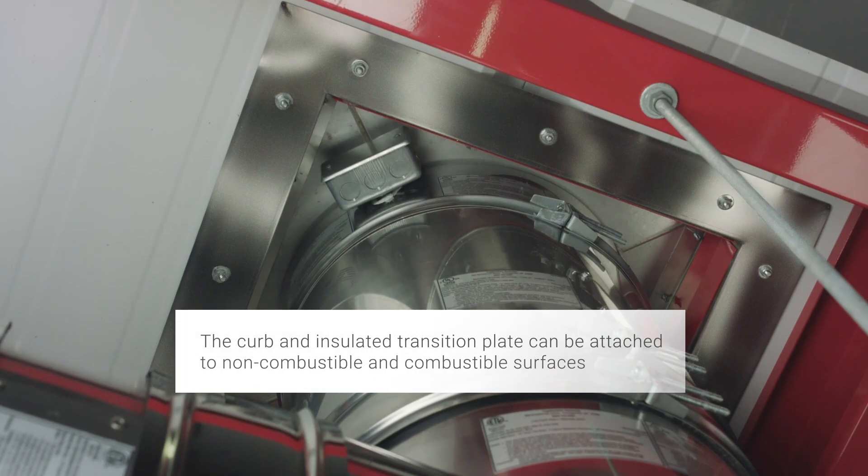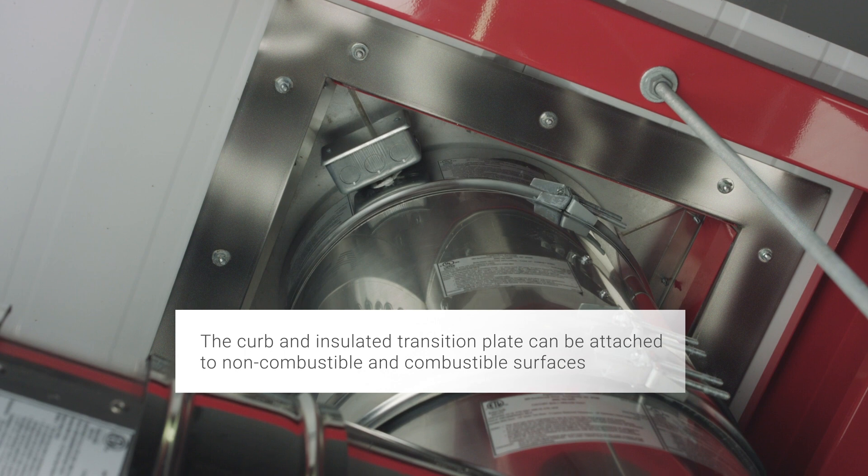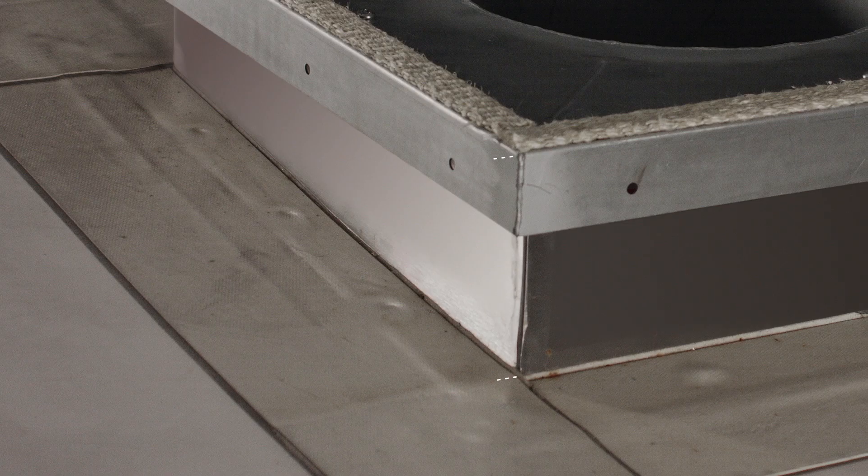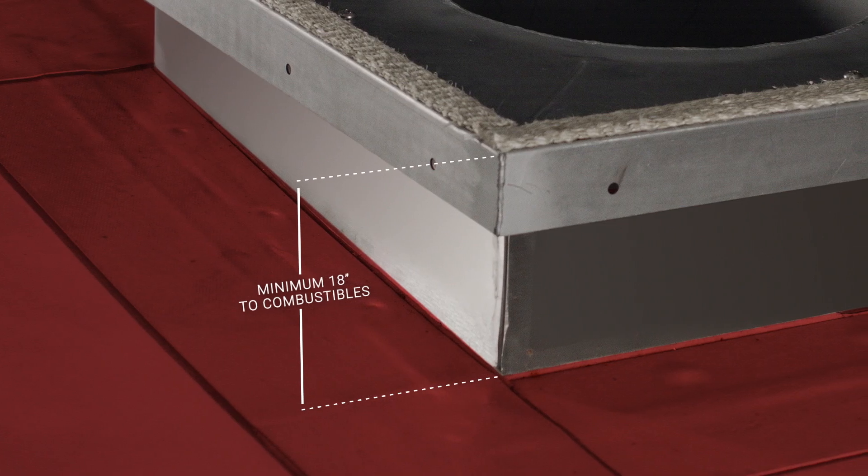The curb and insulated transition plate can be attached to non-combustible and combustible surfaces, but the transition plate must always be at least 18 inches above combustibles.